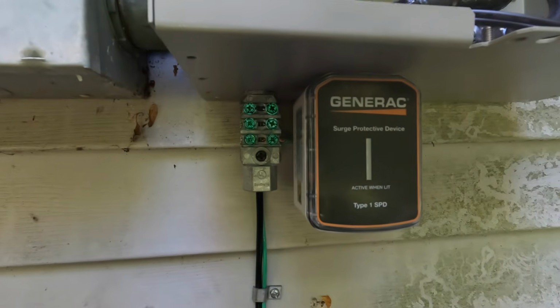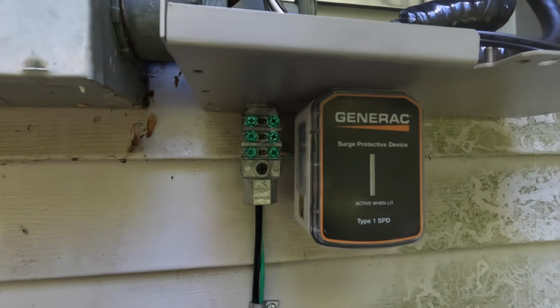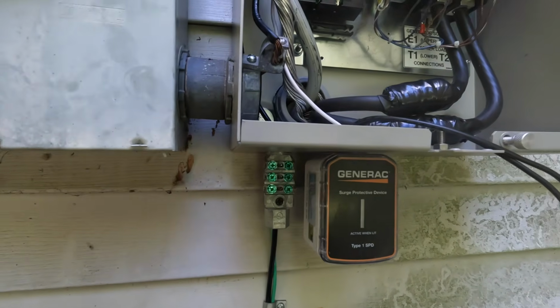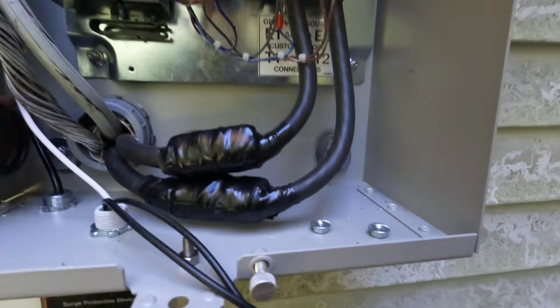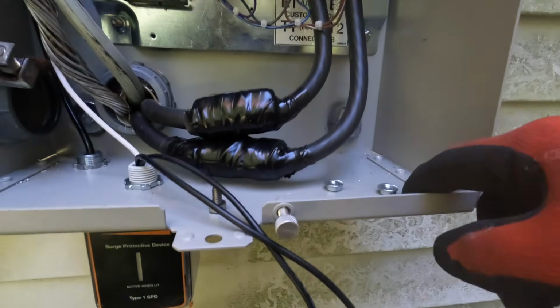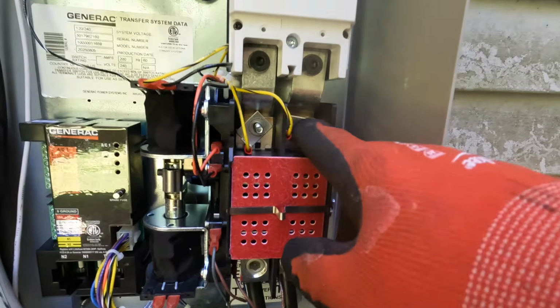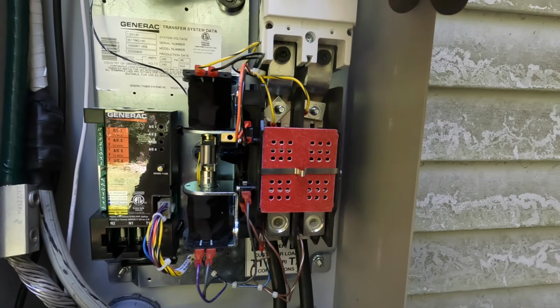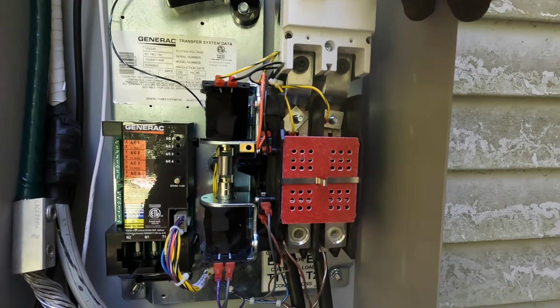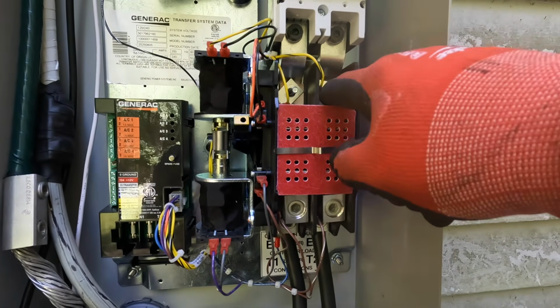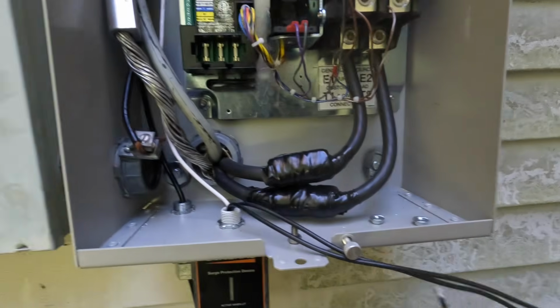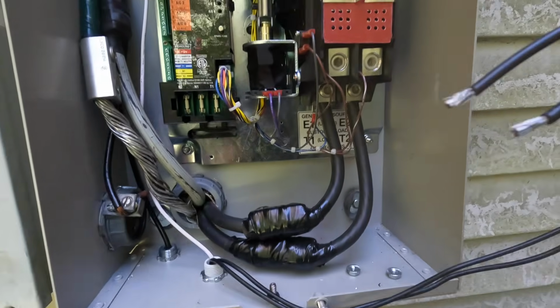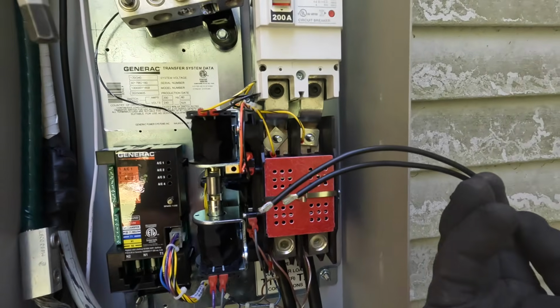I had one surge protection device, Generac, not sure where I got it from. It's been on my truck for a little while. What we're going to do is take off these two nuts right here, which are on the load side of the main disconnect, on these lugs, and then put some crimps on the ends to attach it inside those posts.